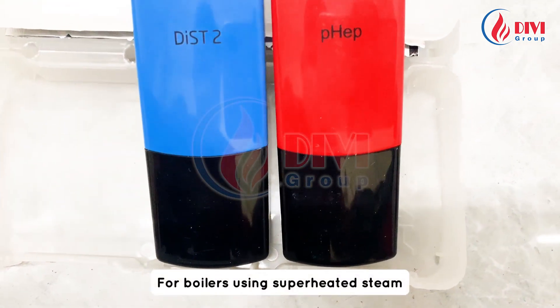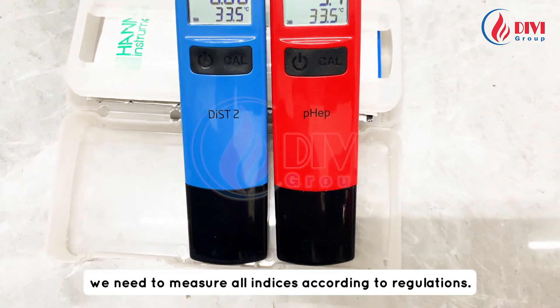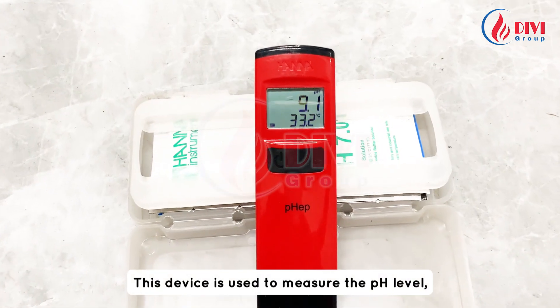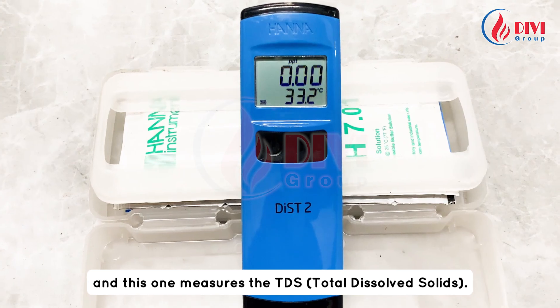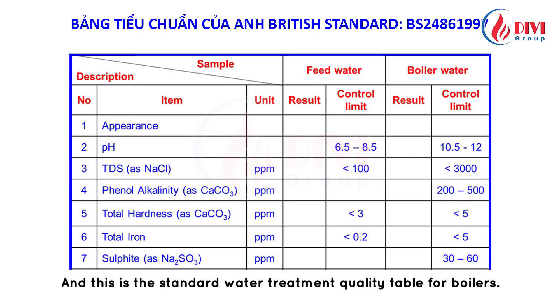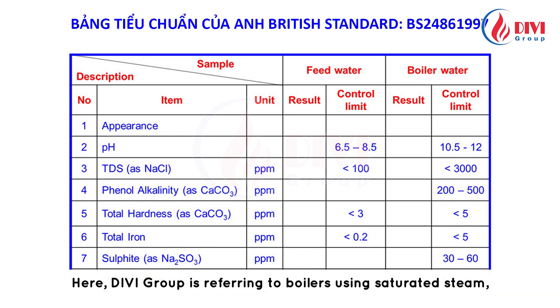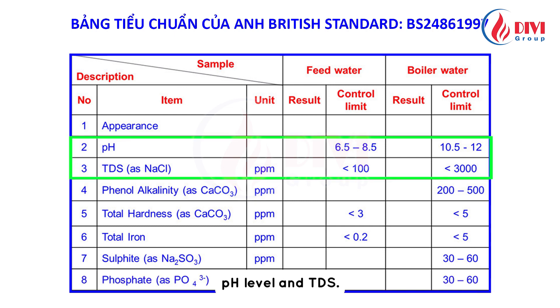For boilers using superheated steam for power generation or high pressure, we need to measure all indices according to regulations. This device is used to measure the pH level, and this one measures the TDS — total dissolved solids. This is the standard water treatment quality table for boilers. DIVI Group is referring to boilers using saturated steam, so the two main indices we need to pay attention to are pH level and TDS.